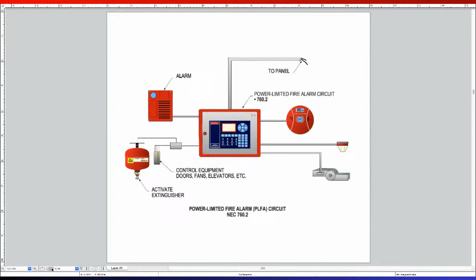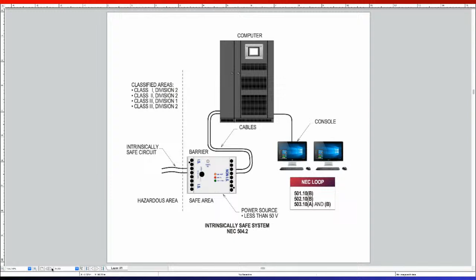This is something a lot of people never see: the type of power source you'll find on the job for an intrinsically safe circuit, less than 50 volts. This power device looks just like this with all the indicator lights, but it'll be marked on one side non-IS, meaning non-intrinsically safe on that side, and then marked IS for intrinsically safe on the other, hazardous side. We spent a lot of time going through this.